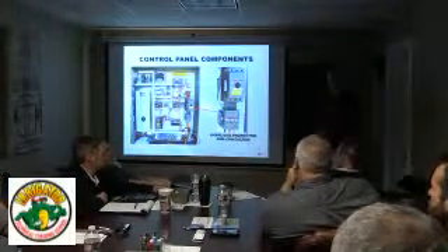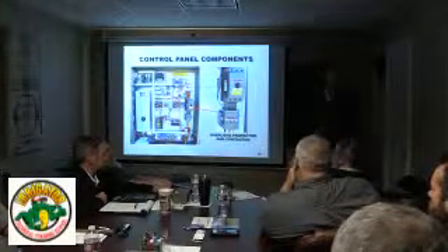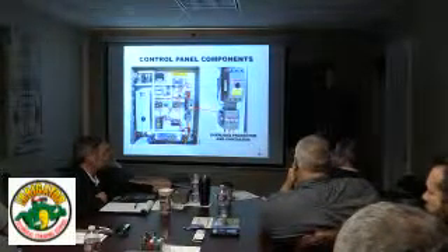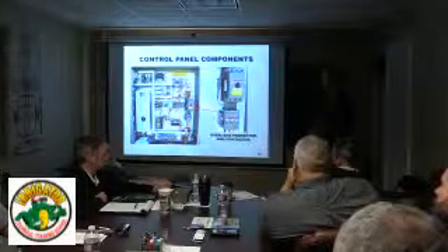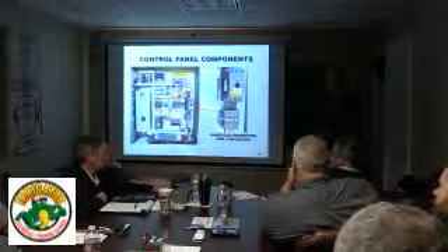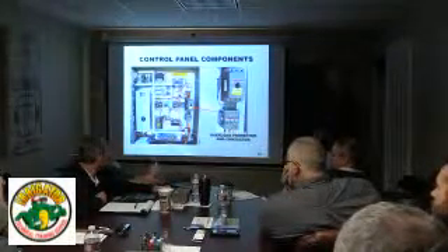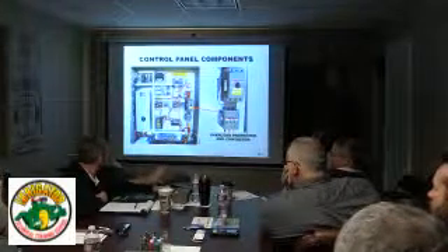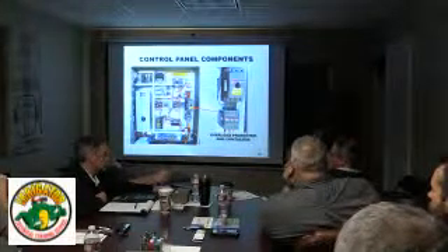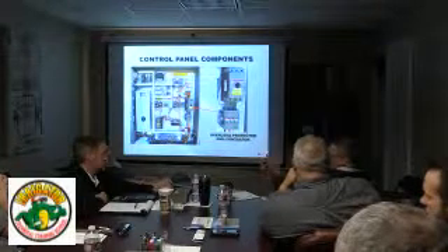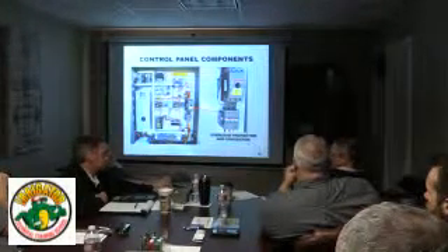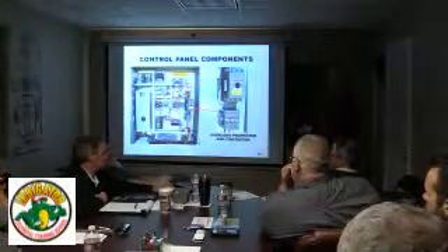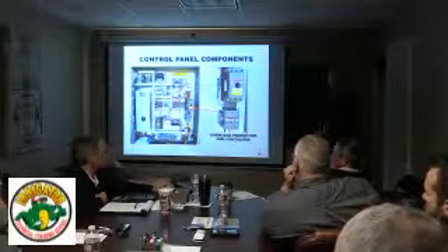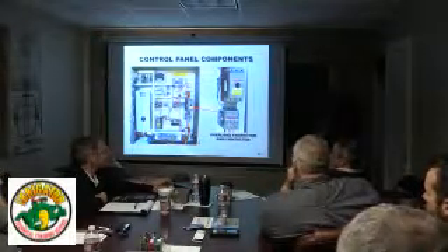Except for the drive, I think, if the wrong leg goes out on the drive, it's just going to die. That's a known issue on ABB. On ABBs too, it doesn't matter. It does happen, because they tap off just one of the two legs to get their step down. U1, on the very left-hand side, that first input. I think if you lose that, then the drive goes.